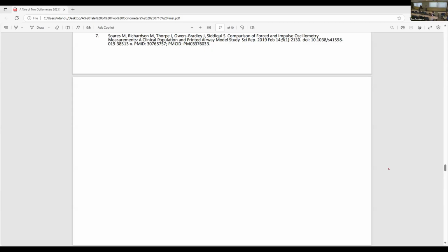Okay, so that's good. So that should have matched it at the higher impedance, except for one thing. The Resmon calibrates with the filter in place. That's right. The Tremoflo does not. So it's very important you use the appropriate filter.